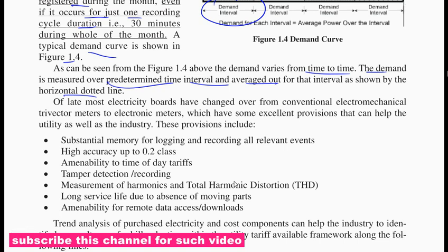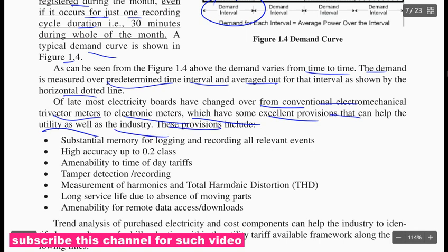Of late, most electricity boards are changing from the conventional electromechanical trivector meter to electronic meters. These have some extended provisions that can help the utility as well as the consumer: substantial memory for logging and recording all relevant events, high accuracy up to 0.2 class, amenability to time-of-day tariff, tamper detection recording, measurement of harmonics, total harmonic distortion, long service life due to the absence of moving parts, and availability of recorded data for download.